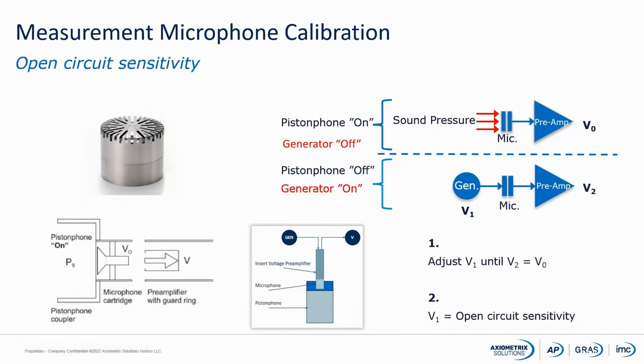When we have done this, then we will actually measure the output voltage of our generator, because the output voltage of our generator is actually equal to the open circuit sensitivity of the microphone. So for measuring the open circuit sensitivity, we are using an insert voltage preamplifier, and then we are doing it in these 2 steps. Step 1, where we are measuring with our piston phone, and then we switch off the piston phone, and then we connect our generator at the same frequency, adjust the level of the generator until we have the same output as we had with the piston phone measurements, and then we measure the generator level.